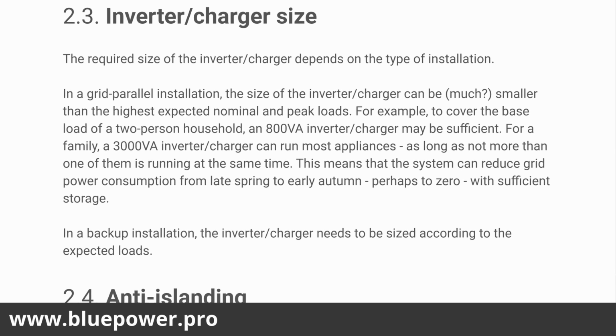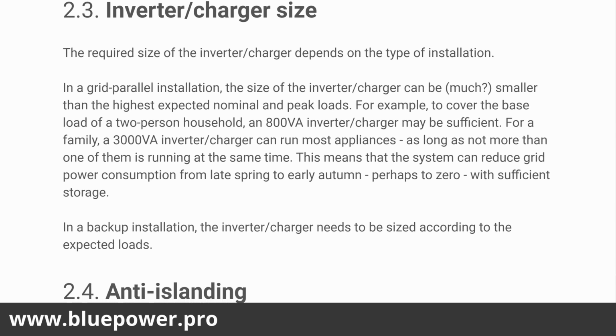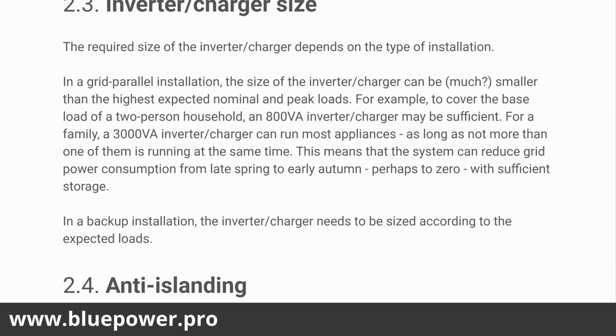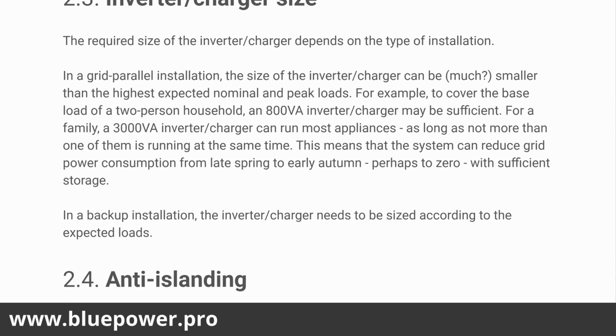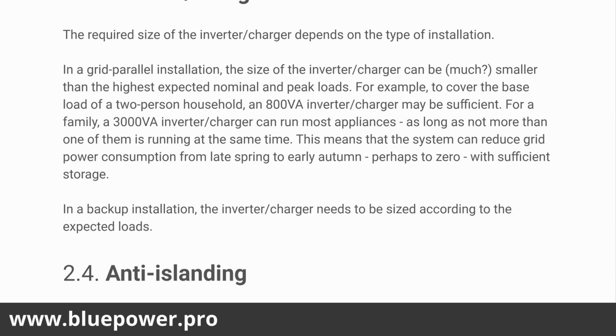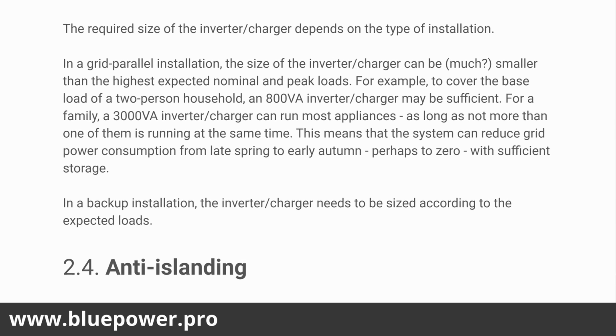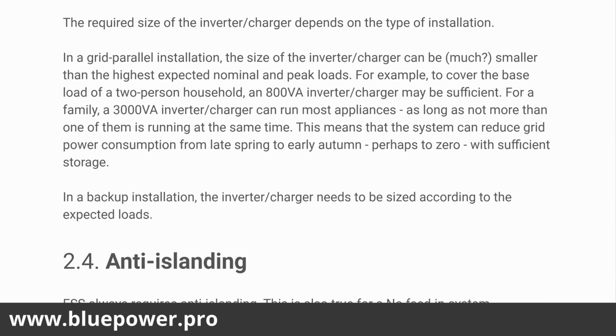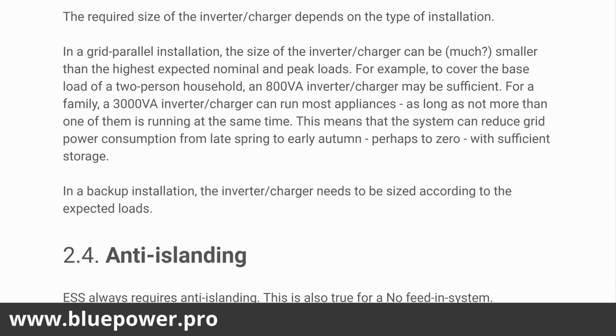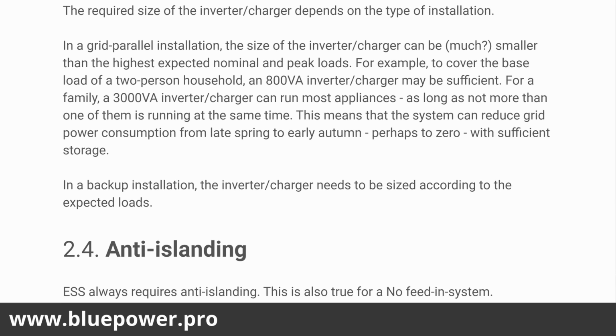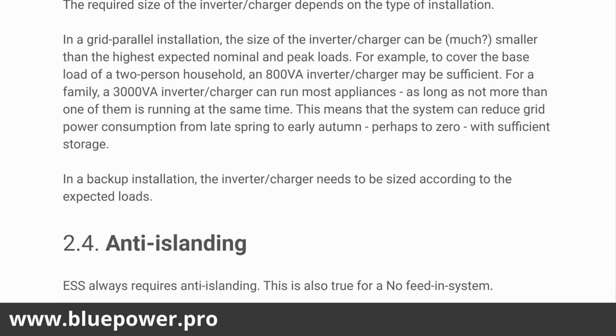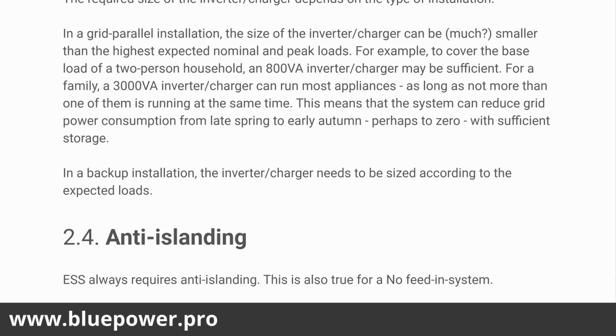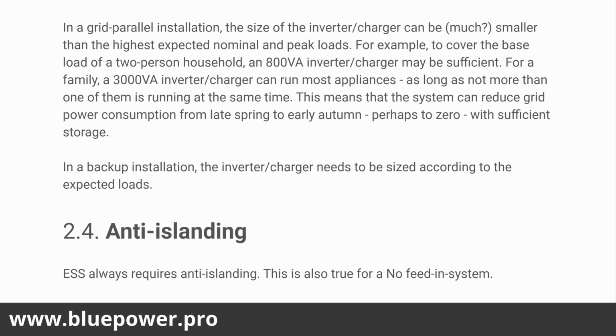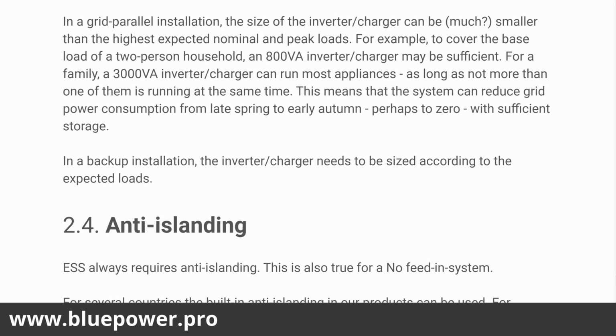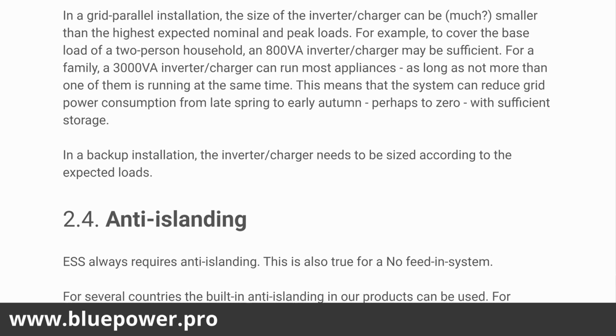So inverter charger size, the required size of the inverter depends on the type of installation. If it's grid paralleled, you're going to be able to feed some of your non-essential loads that are connected before the inverter. And if it is just connected as a normal backup for an ESS installation, you're going to be limited to the power of the inverter that you're going to be able to feed.